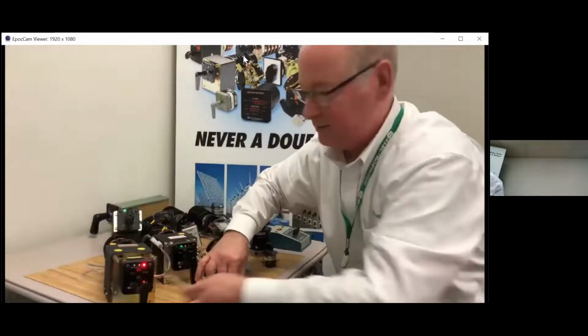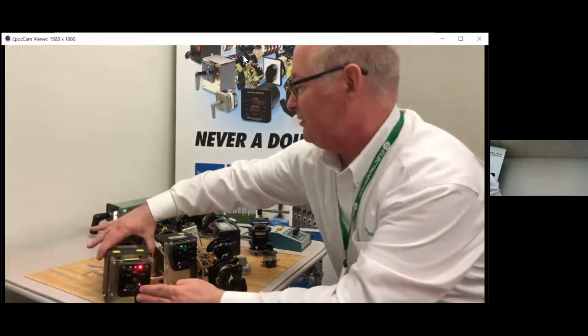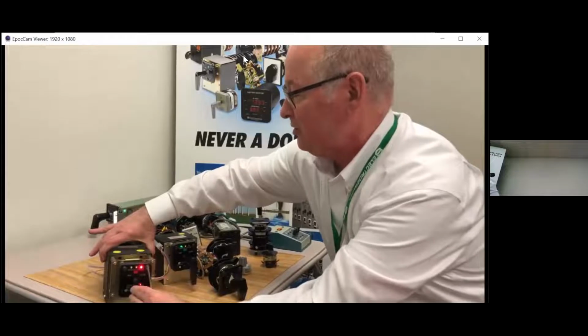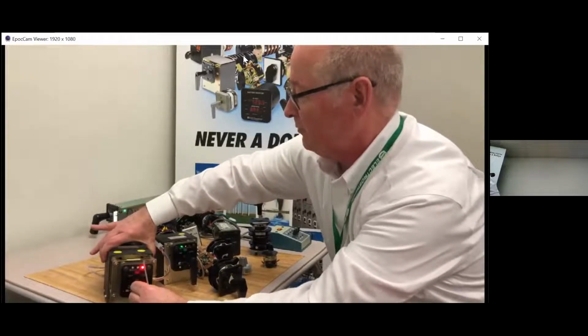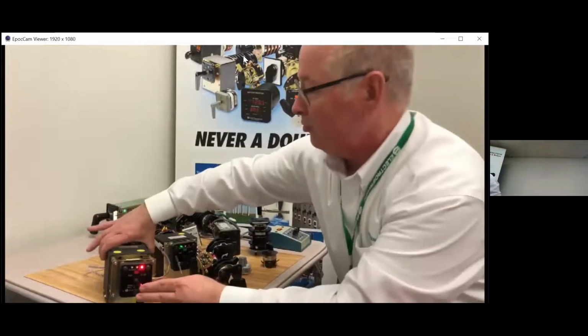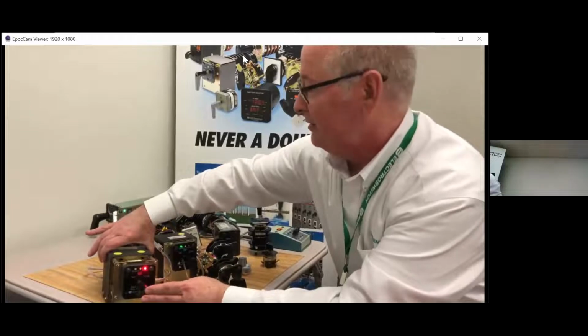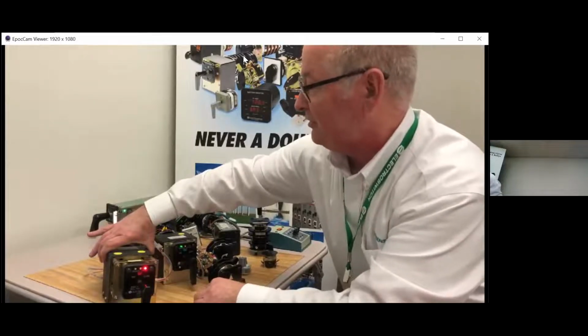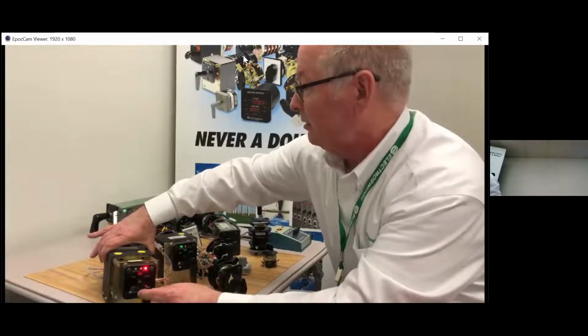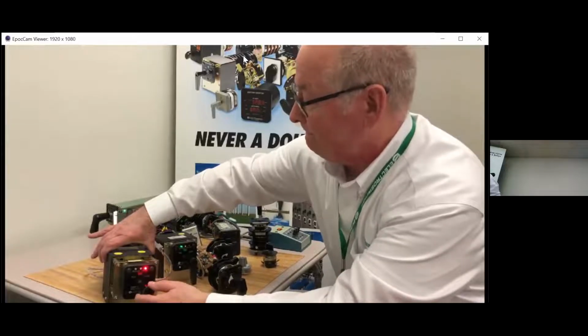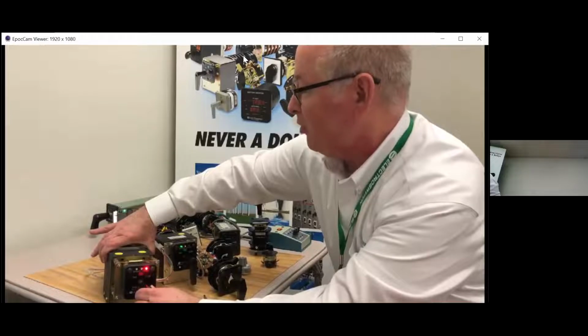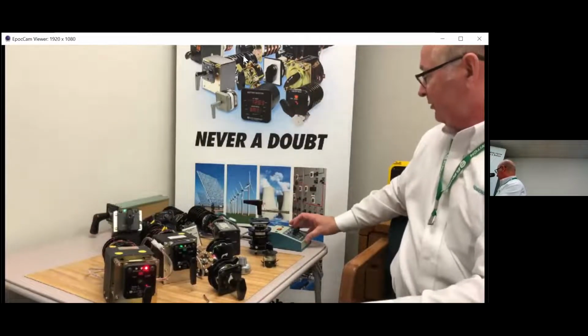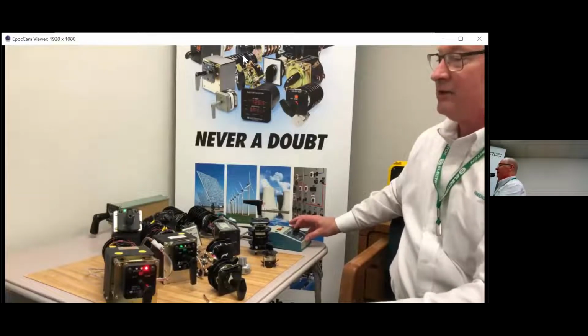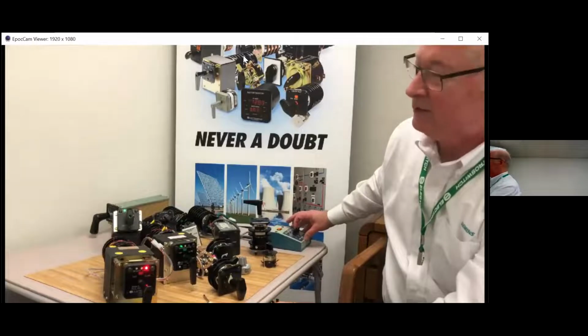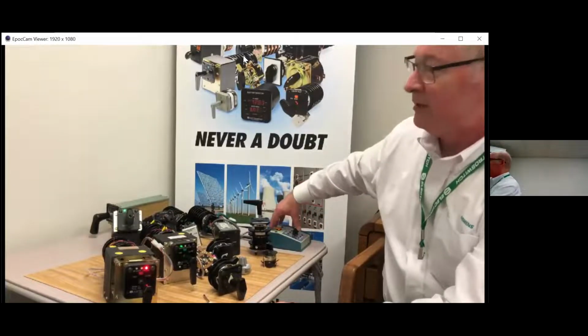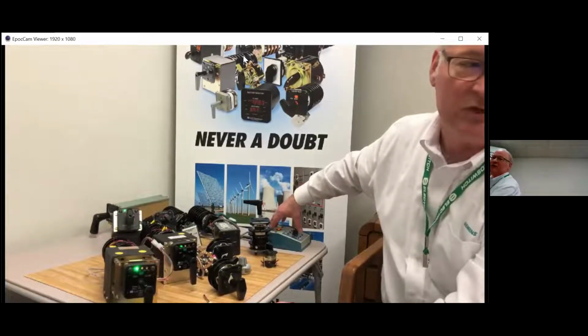I'm going to bring up here the control switch. This happens to be a remotely operated switch. So I have a local and a remote operation. So I'm going to, in a local mode, because it's electrically operated, it would allow me to manually trip and close this switch. So if I'm in the remote mode, I can electrically operate this switch and it will give it a momentary close and then a momentary open. So now I can go in and close that switch remotely.